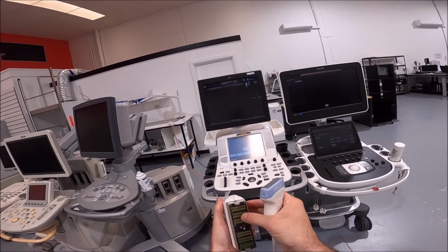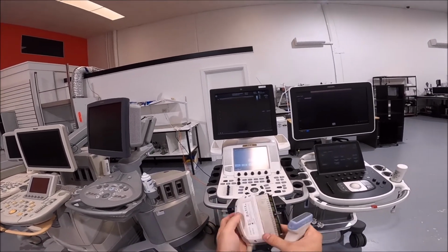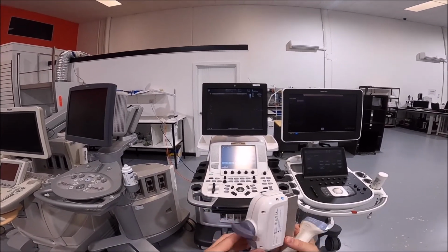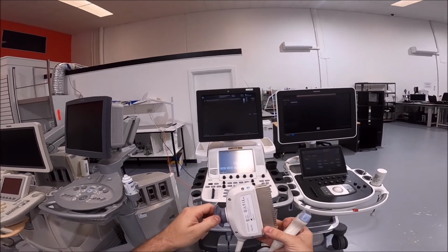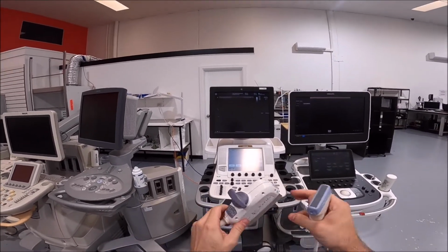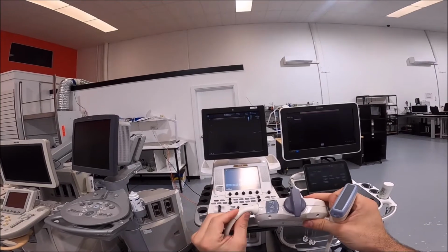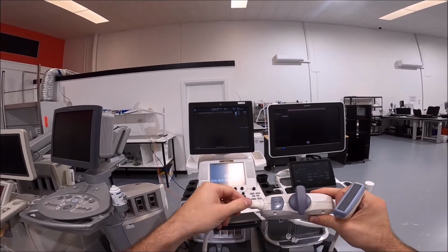So just check any pin surfaces, make sure there's no signs of damage. Check around the sides of the connector, make sure there's no water ingress. Check the locking mechanism works nicely. Check the strain relief, make sure it's still bendy like this one. If it's hard, it needs replacement.